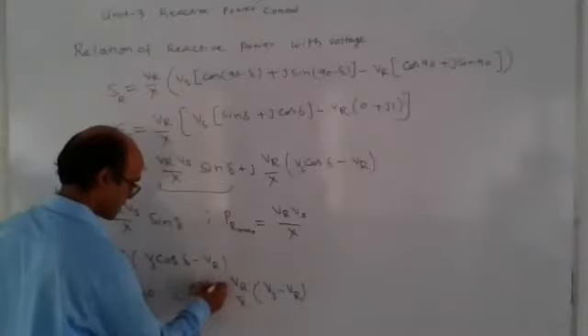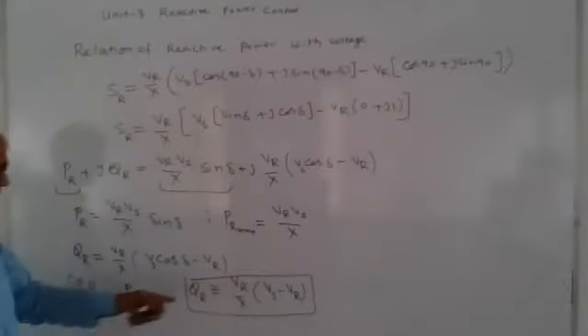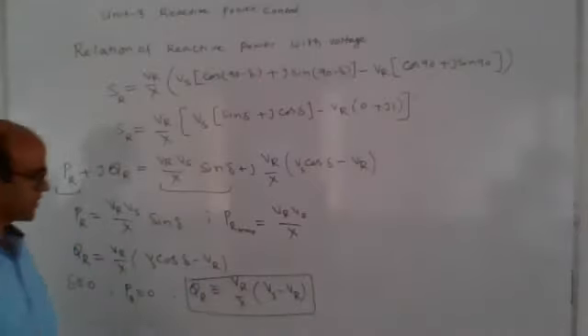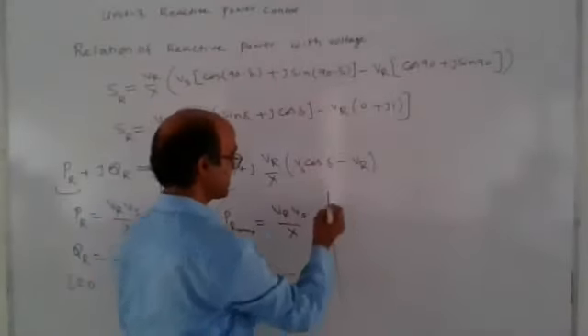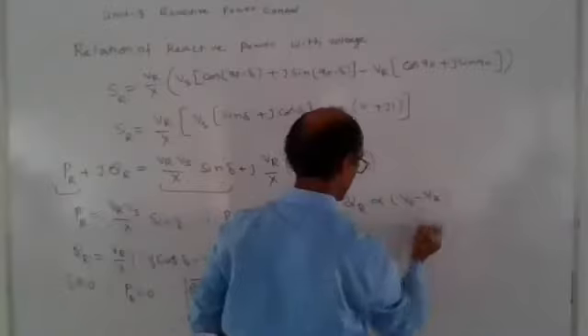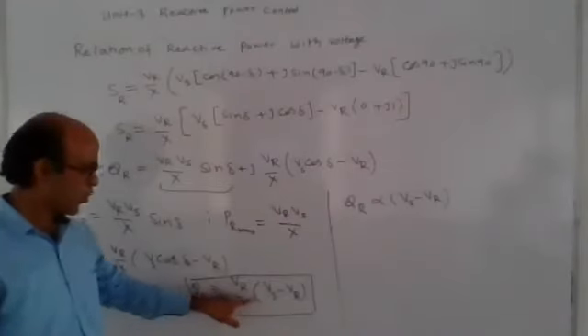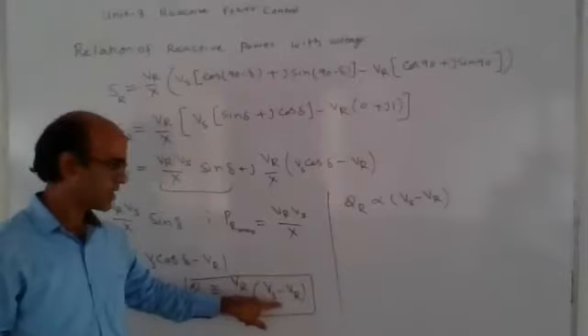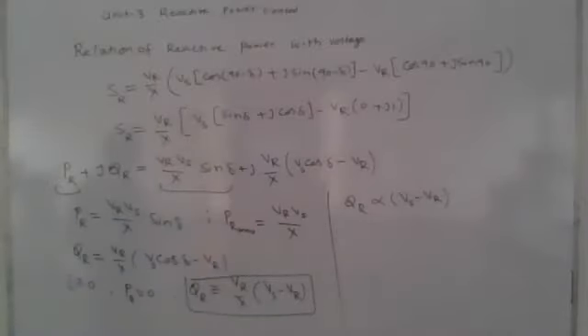So this is the approximate QR. From this expression, VS minus VR represents the change in voltage — the voltage deviation. If VR is held constant, reactive power is directly proportional to VS minus VR, because X is fixed for the transmission line. So by changing voltage, we can control reactive power.